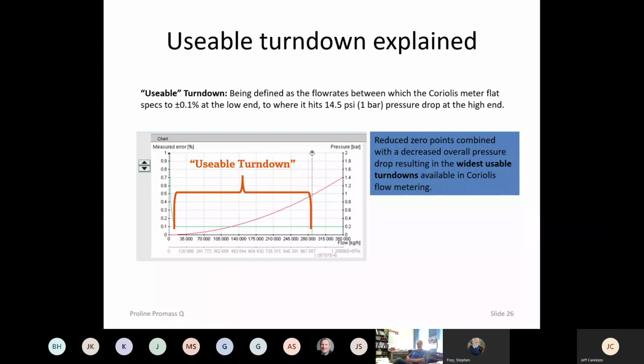Okay, I saved the hardest one for last, so if I don't get to it, that's fine. But I want to talk about usable turndown. And that's basically in a Coriolis meter, you know you're going to get some pressure drop. We rate the meter to 0.1% accuracy of reading. So what's that usable turndown between a 14.5 pound drop to where we no longer can achieve 0.1% mass flow accuracy? We call that usable turndown.